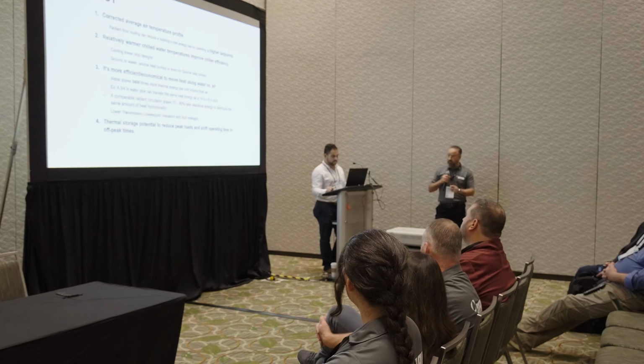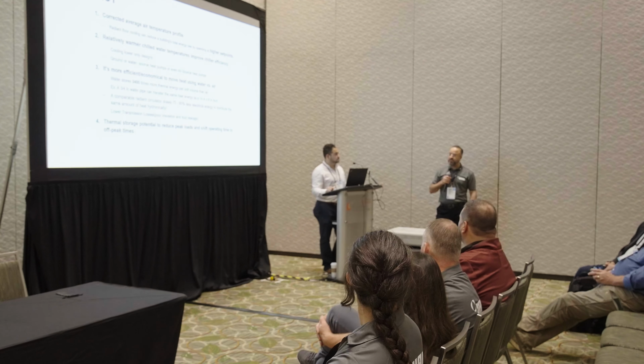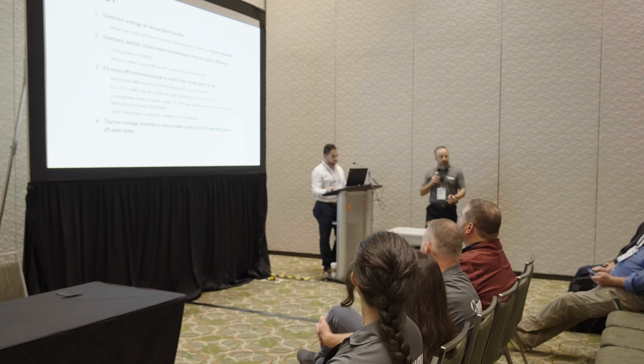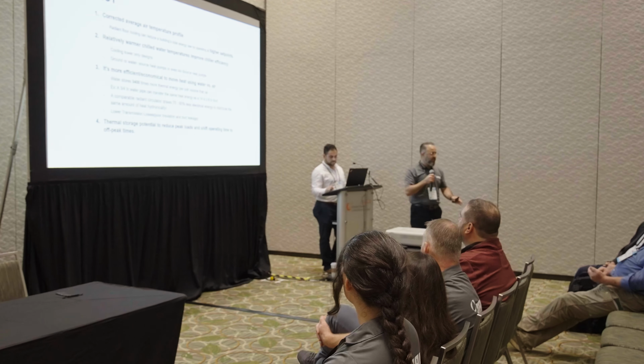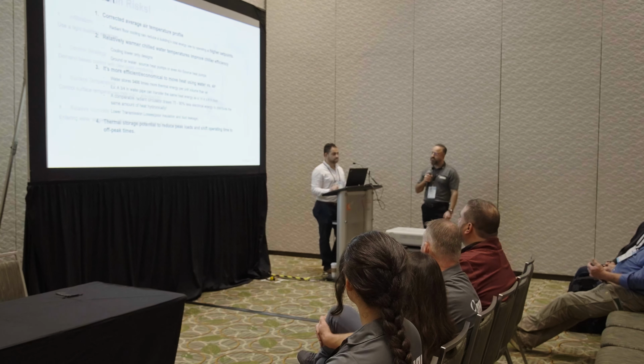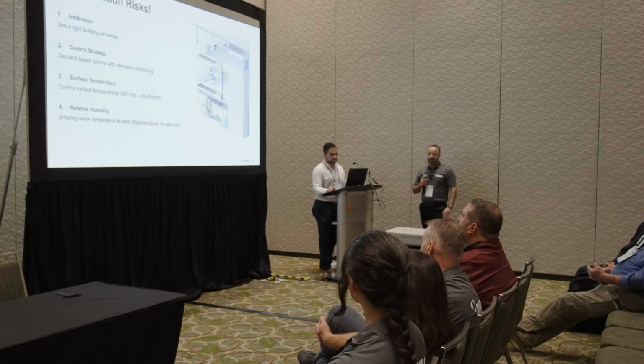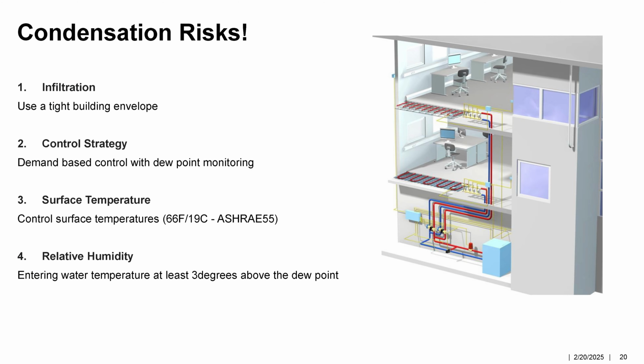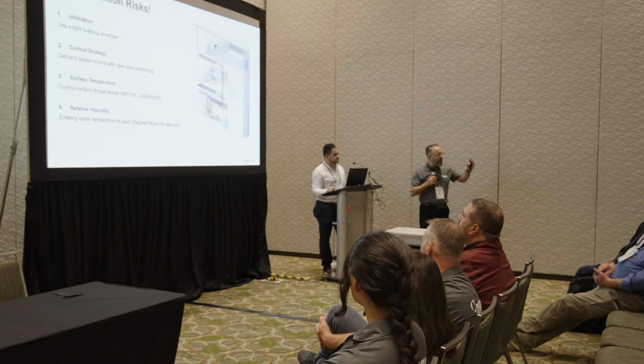And also, Carlos is going to talk about this. You have opportunities for thermal storage, for load shifting using the high thermal mass, as in radiant system application. I know you may already be thinking about the condensation risk. First of all, we don't want to see it in residential application. Second, if you are using it in a commercial application, make sure you go with a tight building envelope, so minimum infiltration. Second, please define a nice control strategy where you are monitoring the dew point.